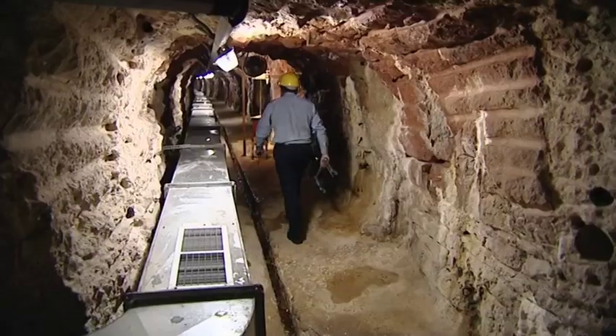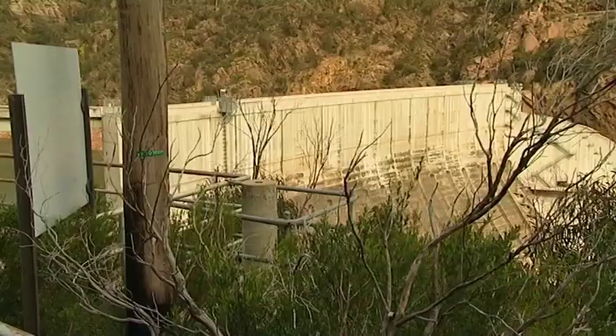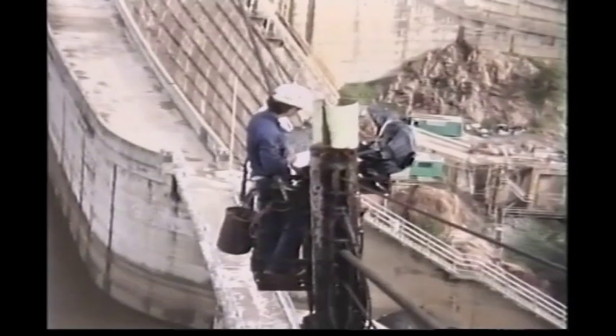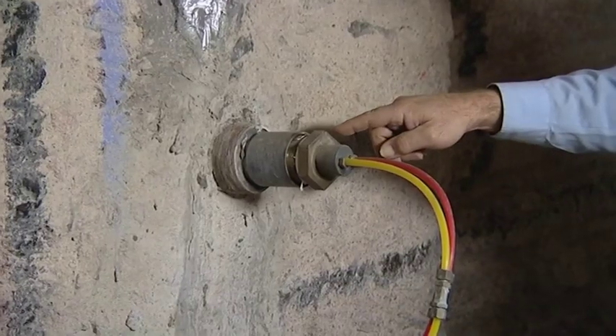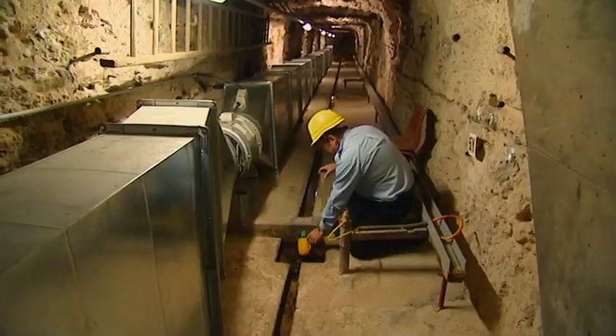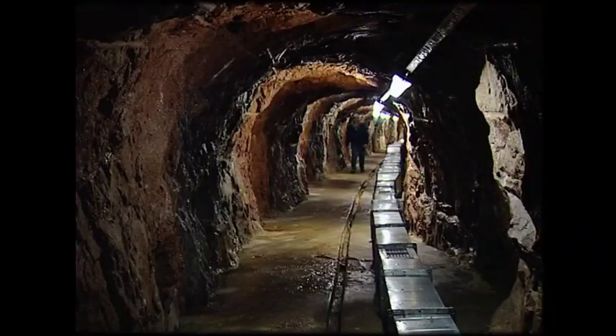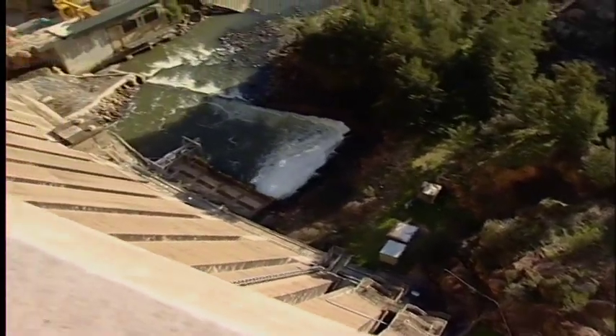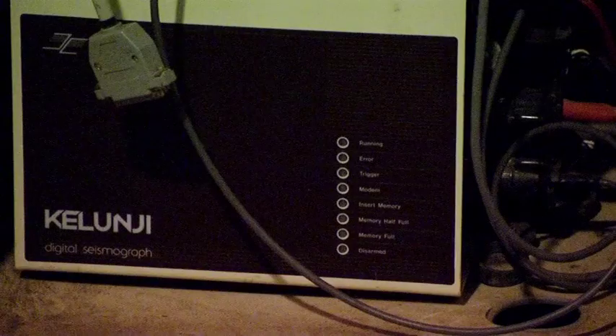The dam structure is continually monitored by daily visual inspections and surveillance instrumentation systems, and survey points are measured annually to ensure it hasn't moved significantly. There are also inspection points inside the dam wall where seepage is measured, along with the amount of water trying to lift the dam from its foundations. The wall itself has a degree of elasticity to protect it from cracking in the event of an earth tremor, and it has an annual movement of about 16 millimetres.